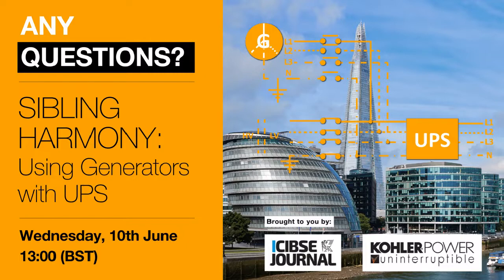Lifts, elevators are typically life safety situations, not always, but typically. So therefore, the fault clearance capabilities of the UPS have to be able to clear the downstream faults in the event of emergency, i.e. on battery. So that's a big consideration.